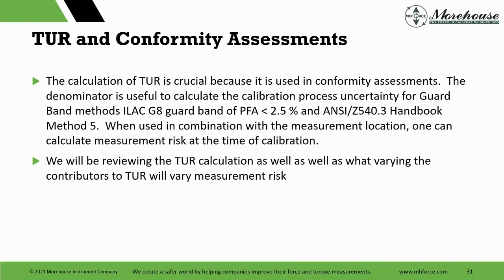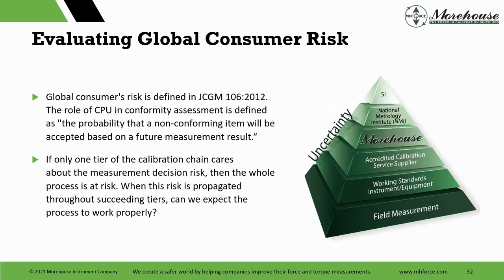When used in combination with a measurement, one can calculate measurement risk at the time of calibration. So we'll start reviewing some things here. Global consumer's risk. This is defined in JCGM 106. And it's the role of calibration process uncertainty, that's CPU, in conformity assessment. That's our denominator of the TUR equation, just so we know. And it's the probability that a non-conforming item will be accepted based on the future measurement result.